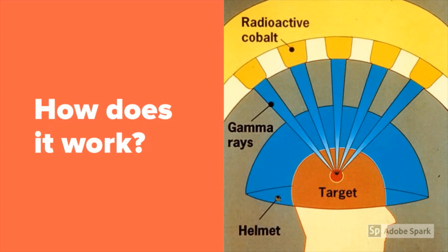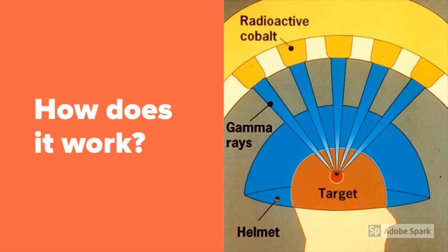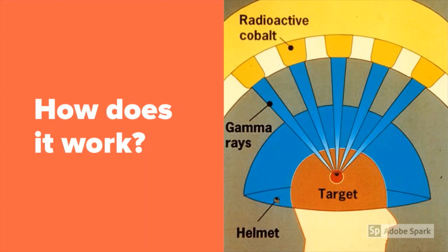Most of the interaction between radiation and irradiated tissue can be expected to be mediated by the Compton effect. The energy level of this radiation is sufficient to give it a high power of penetration. It has a low linear energy transfer. The narrow beams essential to the technique are produced by the collimators, which force the radiation through collimators in the form of small metal tubes mounted in the machine's helmet. The size of the collimator is defined in terms of the diameter of the 50% isodose around the center of the target.